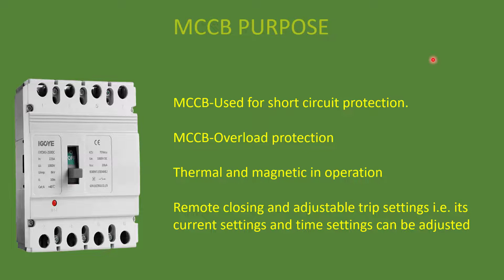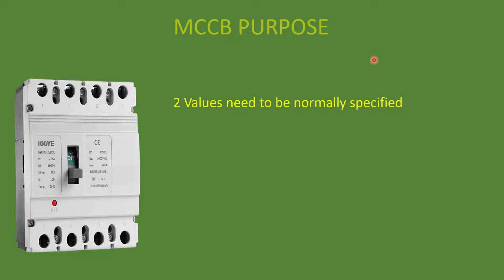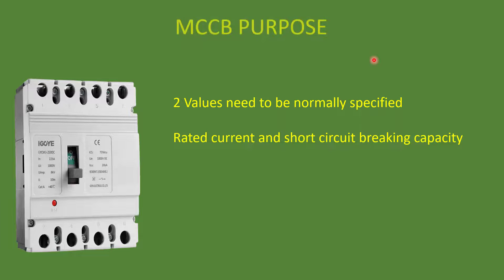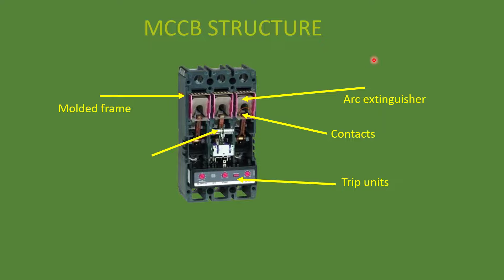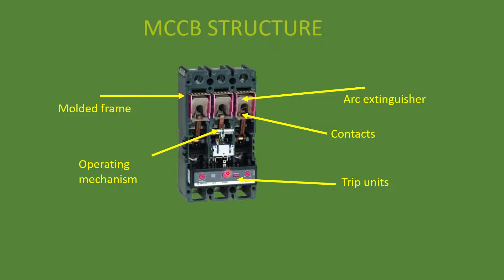It is used in sub-main or main distribution boards. When buying an MCCB you must specify two values: the rated current, which is the maximum allowable current, and the short circuit breaking capacity — the maximum short circuit current it can withstand. The parts of MCCB are almost the same as MCB: arc extinguisher, fixed and movable contacts, trip units, molded frame, and operating mechanisms. The key difference is that MCCB has remote closing and adjustable trip settings — the operating current range and tripping time can be adjusted and it can be operated remotely. The operation is also the same as MCB, with a magnetic coil and piston for short circuit protection and a bimetallic strip for overload protection.